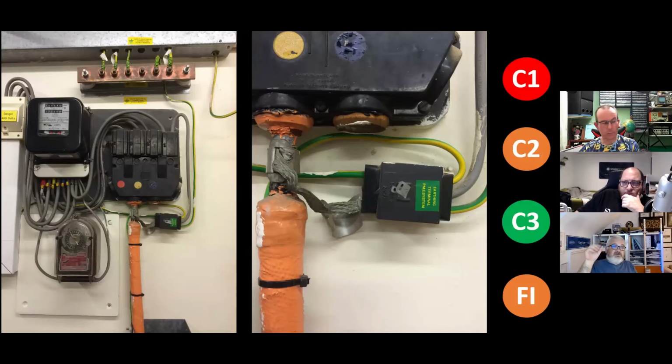Now, when you take any conductor for earthing, you'll have a volt drop or an R2 value. And if you have two conductors at two different potentials and two different impedances, you can get a potential difference across the two. The only way of mitigating that is by linking them with a supplementary bond, which creates spinning circulating currents potentially. And guess what, guys? This is also mentioned in the DNO documents. It's buried. Honestly, my head's been frazzled with this stuff over the last couple of months.